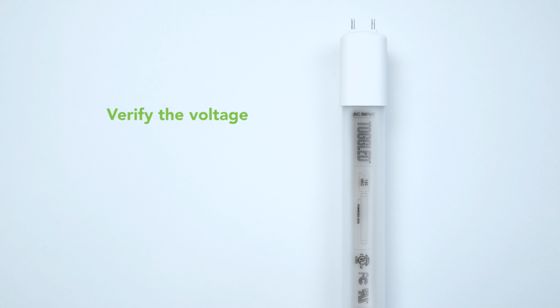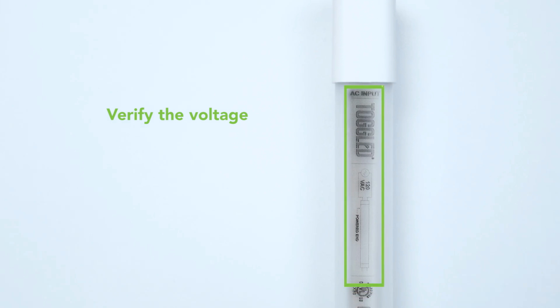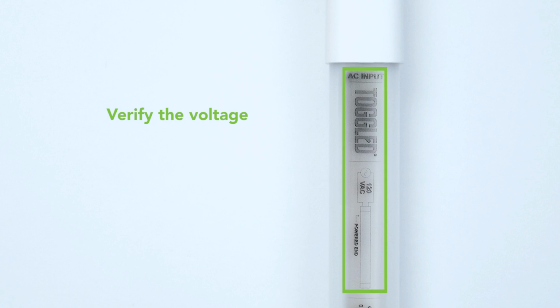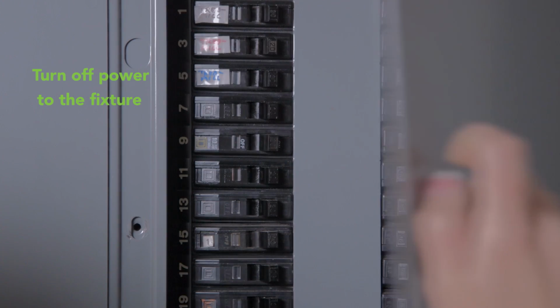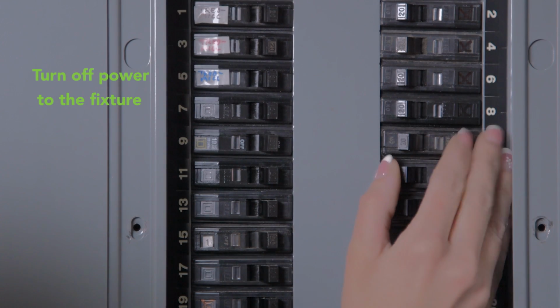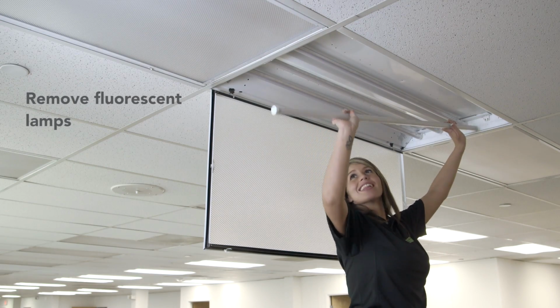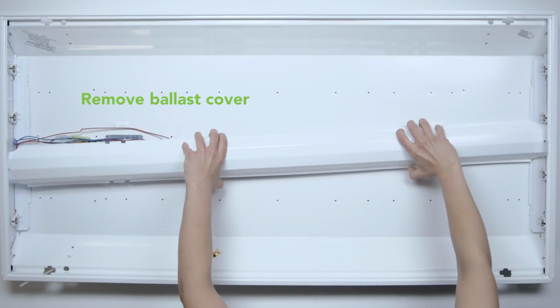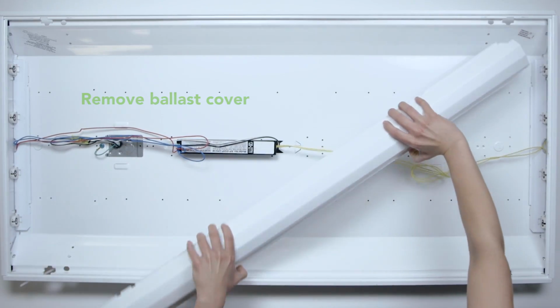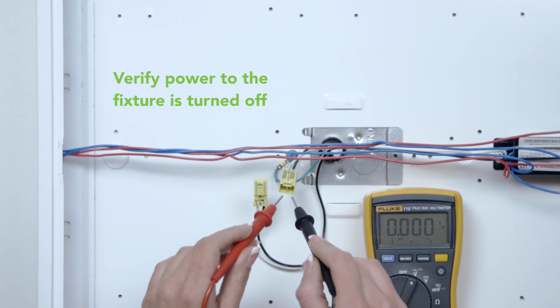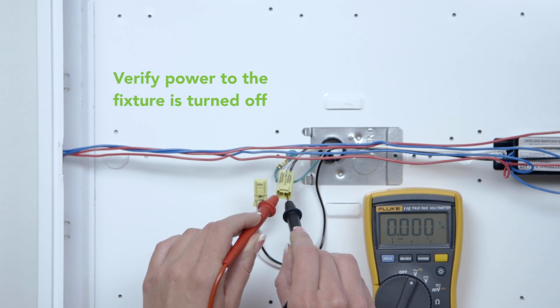It is important to verify that the voltage to your fixture does not exceed the voltage rating marked on the powered end of your Toggled LED tubes. Next, confirm that Toggled tubes are compatible with your fixture. Start by turning off power to the fixture at the breaker. Remove old fluorescent lamps. Remove the ballast cover inside the fixture. You can use a multimeter to verify that the power to the fixture is turned off.